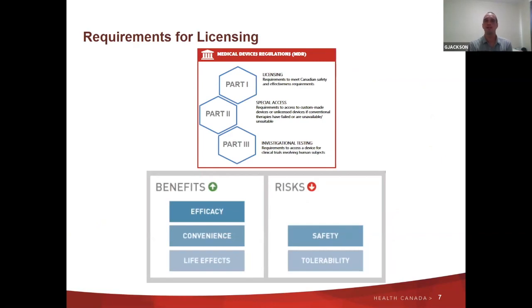The medical device regulations are split into five parts. We primarily look in evaluation at the first three parts, and for typical licenses, specifically in part one. There's a section that looks at the risk and benefits of devices with respect to safety and effectiveness. Effectiveness has to do with the intended use of the device. Most class three and four devices have an explicit intended use or indications for use, and we need to see enough evidence that the device can achieve its intended use in its intended population of use. And then safety is a bit of a spectrum and involves some risk benefit.